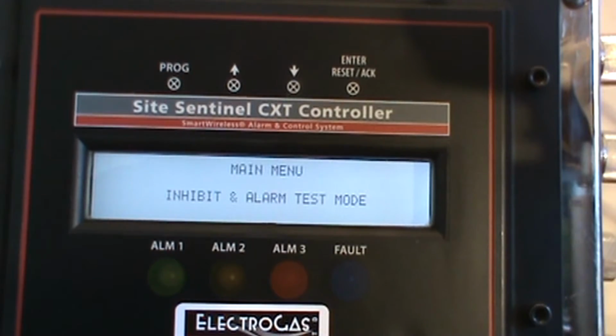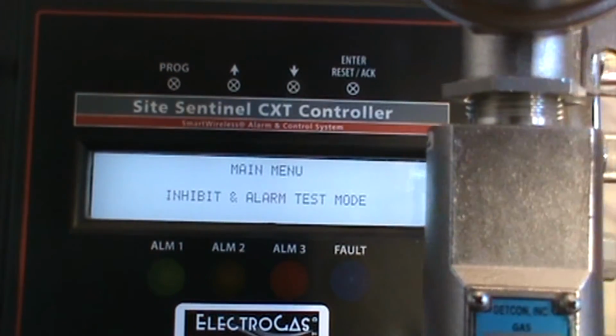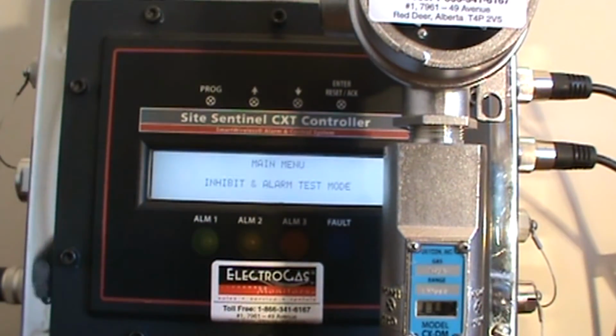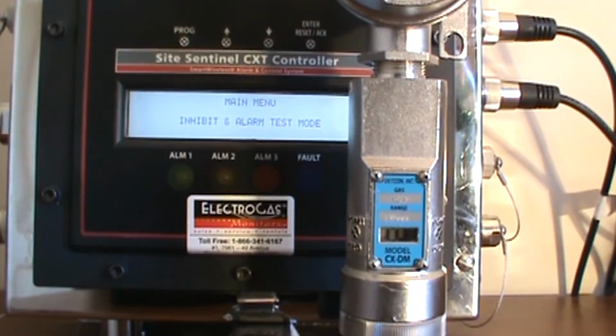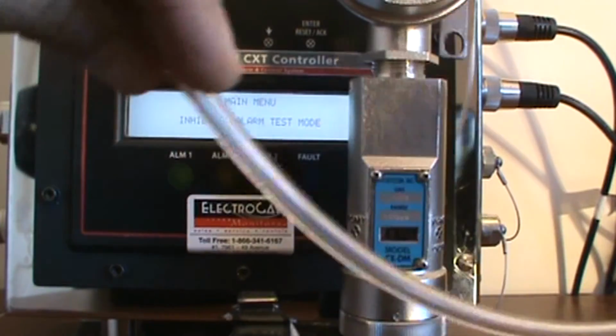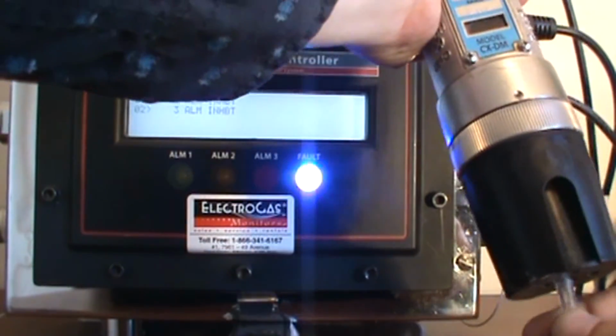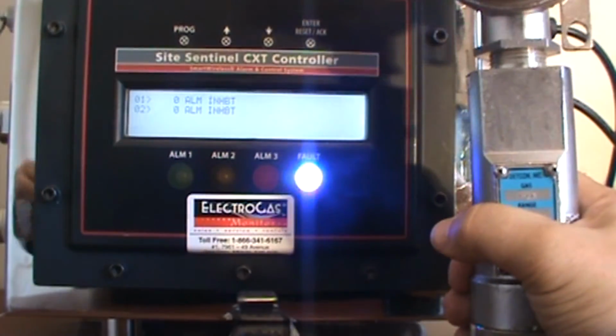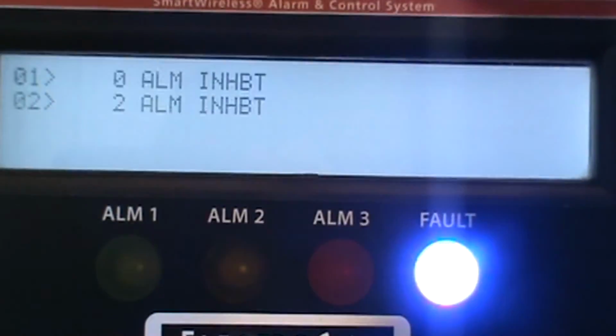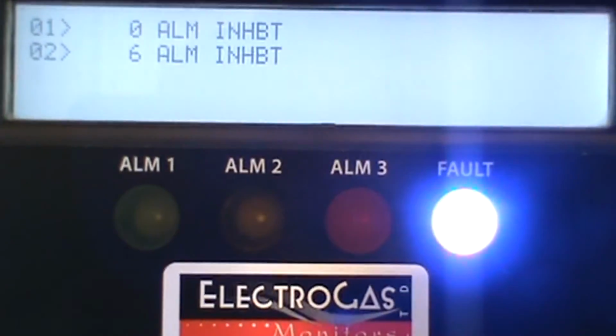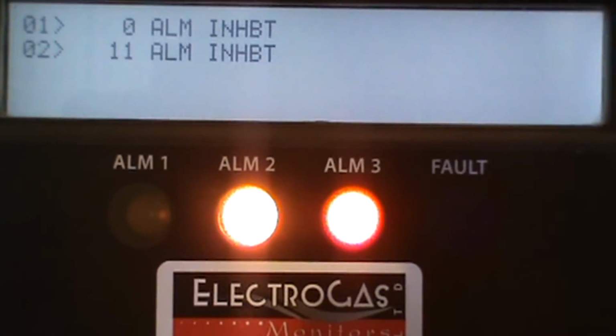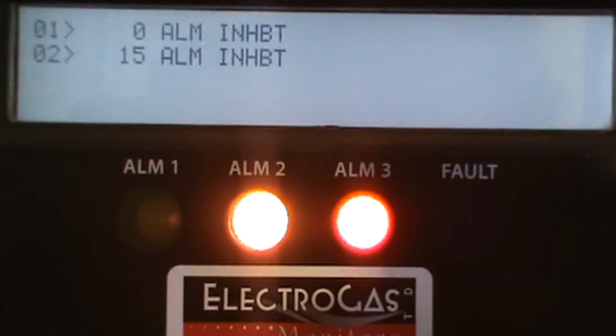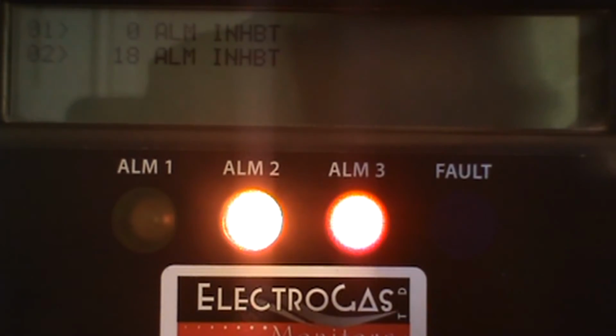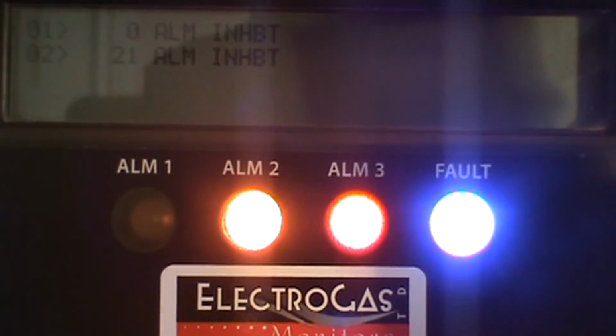No need to go into a special mode. So here's my H2S sensor. I'm simply going to apply gas as I have done in the past without going into any special mode. And now if we look at our display, it says alarm inhibit. So even though I am now in an alarm exposure environment, because I've inhibited my alarm, it stays silent. And that is how you do a proper bump test using alarm inhibits via the onboard menu on your CXT controller.